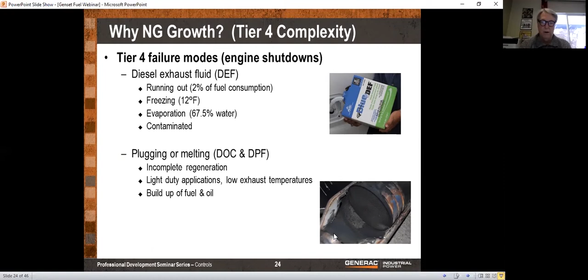We have a customer in California we're working with right now, and they're having a devil of a time. Even though it's a standby generator, California wants a complete selective catalytic reduction system on it, which drives the price up about 50% premium. Even then, they come out and test periodically, and if you don't meet the new standards, they'll say you've got to replace it. They're having to replace a diesel generator that's only 3 years old because California's emission standards have changed and it no longer meets them.